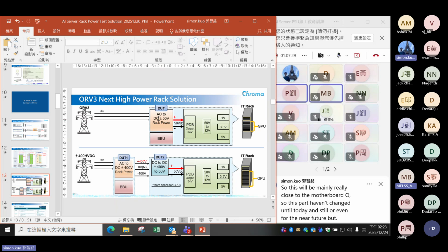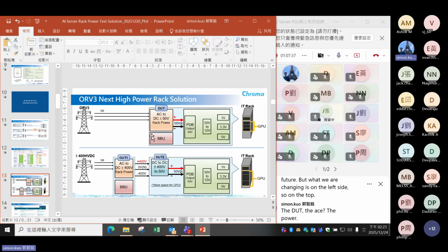But what we are changing is on the left side. So on top, the DUT, the AC/DC, the power supplies, and the BBU are pulled out to a single rack. But since there's a voltage change, you need to add the 400 volts to 50, because in the past, on the left, it never changed, it's still 50 volts. So you need to add something to convert from the plus minus 400 for the rack on the left, and convert it to the 50 volts so it can be used by the green blocks.